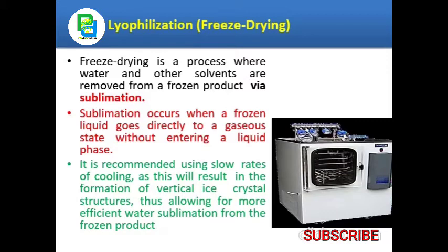Basically, this is the diagram of a lyophilizer. It looks like this, with certain trays in between this structure. It is recommended to use a slow rate of cooling, as this will result in the formation of vertical ice crystal structures, thus allowing for more efficient water sublimation from the frozen product.